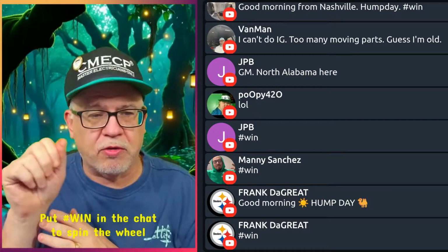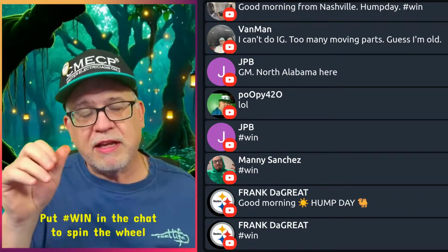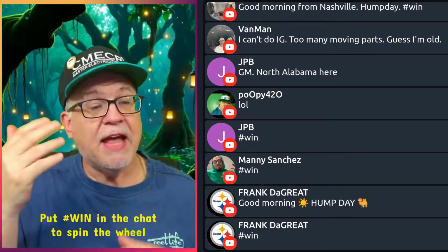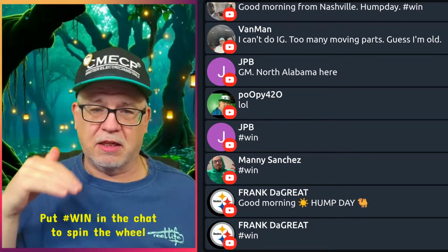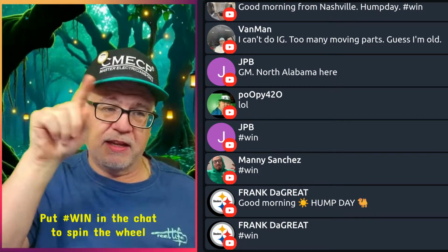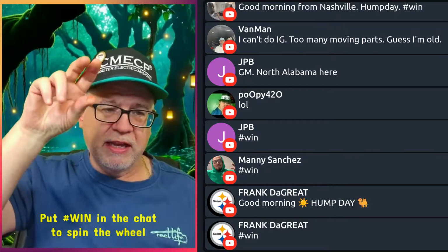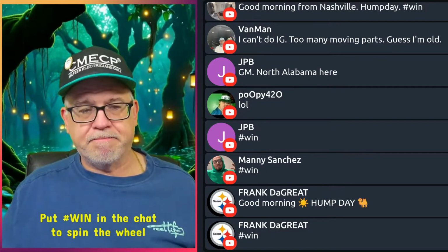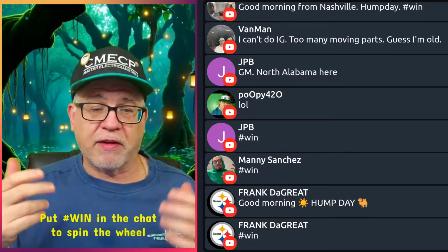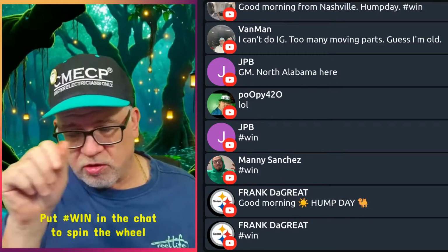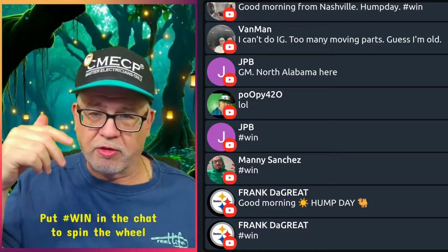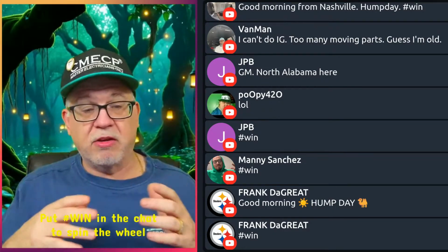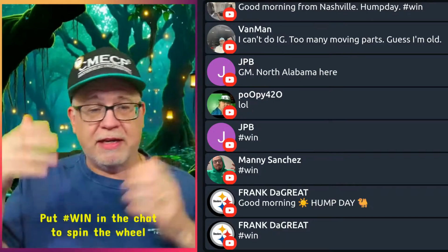Now, most of those panels that are flippable usually have the main breaker that is horizontal, so it doesn't affect it either way. And then usually stamped in it, it'll say line load, and you'll see line, and it'll have a slash, and it'll say load, and that means on both sides. So it doesn't matter which way you install it. Okay, that type of thing doesn't make a difference because all of the overcurrent devices will work horizontally. They won't work vertically, and so you don't have an issue of worrying about the on and the up position issue. Okay, so again, you'll know it when your panel allows you to mount it either way.